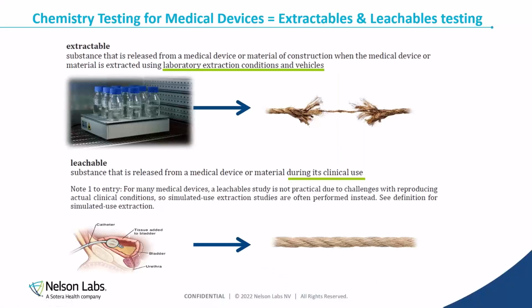When we say chemistry testing for medical devices, we do mean extractables and leachables testing. It's important to understand what are extractables and what are leachables. For the initial chemistry testing on medical devices, we typically focus on extractables. So these are compounds that can be extracted under exaggerated lab conditions. And when we do those exaggerated lab conditions, we do things like using multiple solvents, long extraction times, and high temperatures. This is to assess a possible worst-case exposure condition for a patient on whom the device is used. If the device cannot withstand the exaggerated conditions, then we will justify using simulated use conditions. But we have to try exaggerated first.